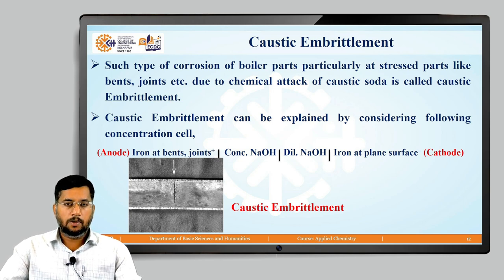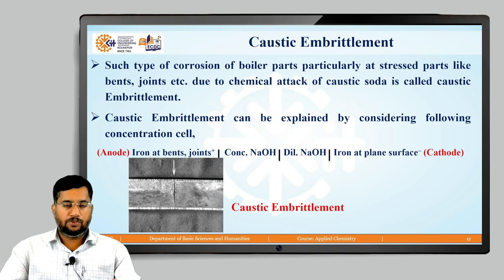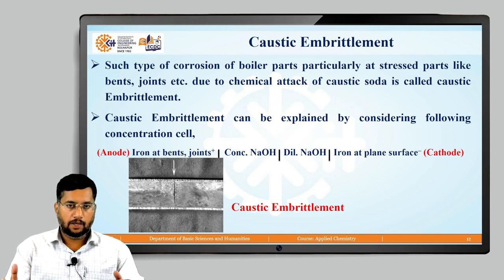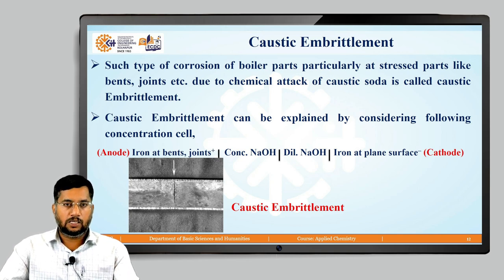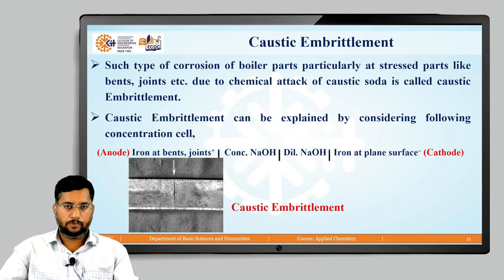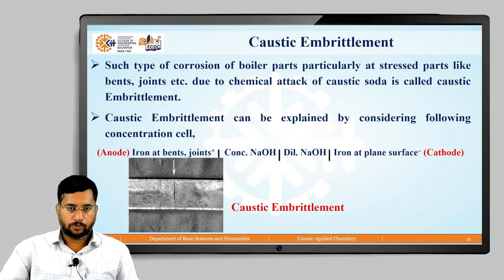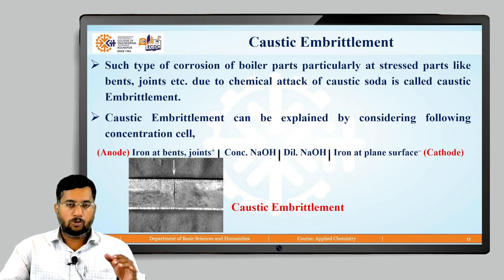Caustic embrittlement can be explained by a concentration cell. At bends and joints where flow rate is low, NaOH accumulates and the iron in contact with concentrated NaOH acts as the anode. The remaining iron parts, where flow rate is high and NaOH is diluted, act as the cathode. This galvanic action causes cracks to form in the boiler material, as shown in the diagram.